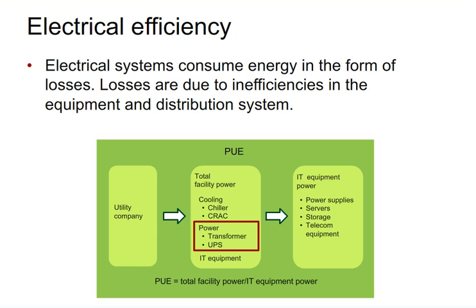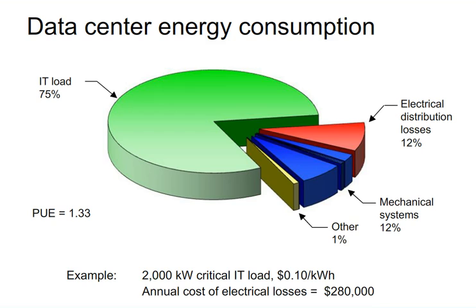When you look at a data center energy consumption with a 1.3 PUE — where mechanical losses have been reduced through containment and heat management — there's still a big piece which is electrical distribution losses, about 12%. For a 2,000 kW data center with an annual cost of $0.10 per kilowatt hour, that comes out to about $280,000 a year just spent on wasted electrical energy. So there's a significant amount of money to be addressed on the electrical side.